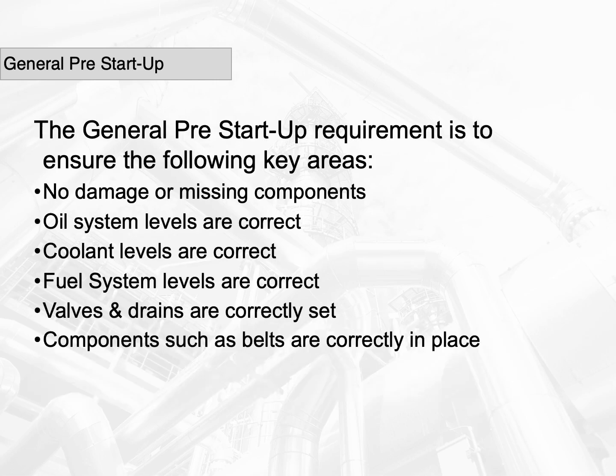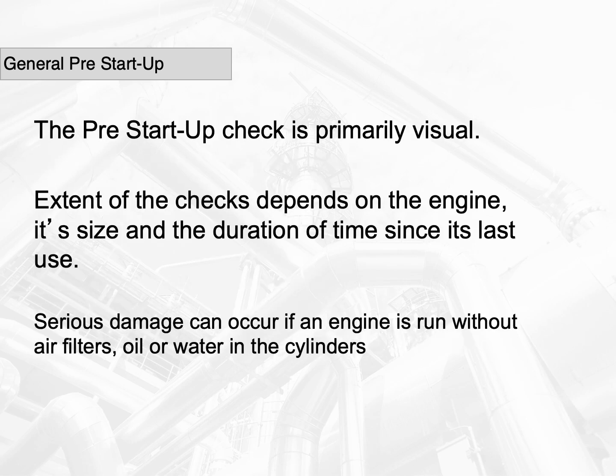The general pre-startup requirement is to ensure the following key areas: no damage or missing components, oil system levels are correct, coolant levels are correct, fuel system levels are correct, valves and drains are correctly set, and components such as belts are correctly in place. The pre-startup check is primarily visual. Extent of the checks depends on the engine, its size, and the duration of time since its last use.